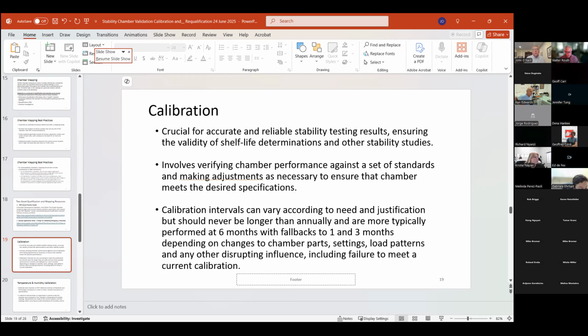But if you didn't calibrate properly, then you start to raise all kinds of red flags with the inspectors. So if it goes well, you can extend the period. I like to see it every 3 months when I was looking at chambers. And if we had 3 consistent periods with passing calibrations, we'd fall it back to 6.